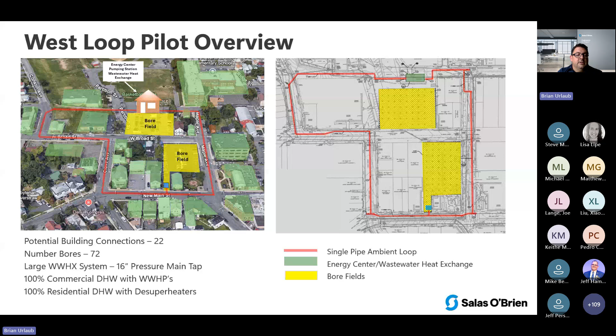And I think this is a 10-inch main for an ambient loop that runs around this particular site. And one of the things to keep in note or to think about when you're looking at these single pipe ambient systems, if one building is driving your flow rate, take that building off and do a parallel system with that building, because like this particular instance, the school was driving the entire ambient loop flow.